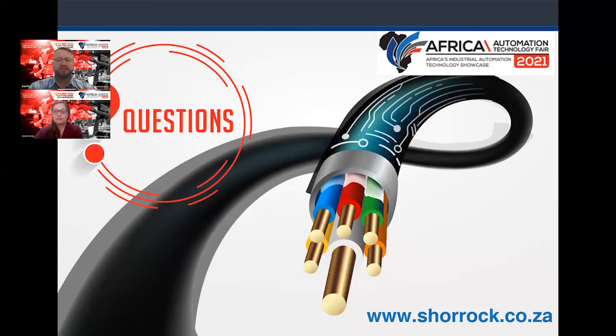But a challenge in the industry is it's not very common to find a 20 amp, a 25 amp, a 30 amp, a 35 amp, and a 40 amp power supply in your series. So for WAGO on the Pro 2, we go from a 20 amp to a 40 amp power supply. But I can easily set up the electronic circuit breaker functionality to operate at 30 amps and have a protection at 30 amps.